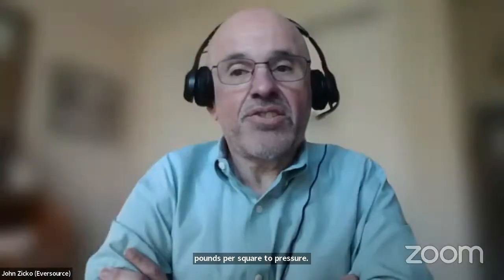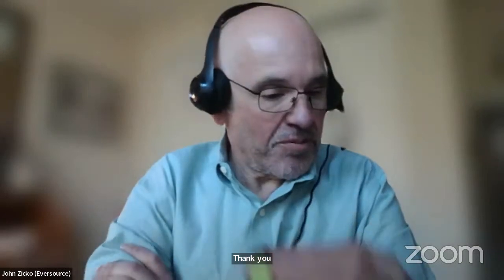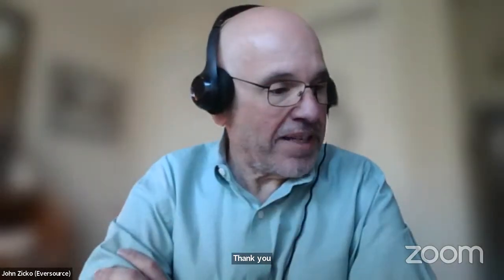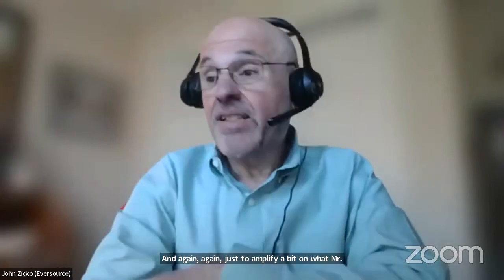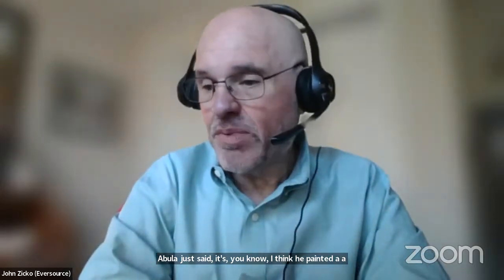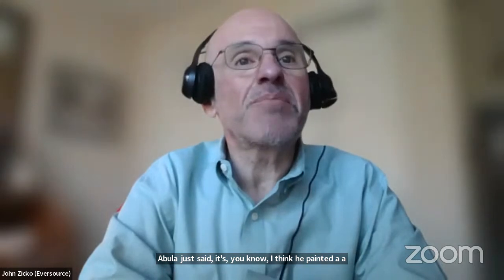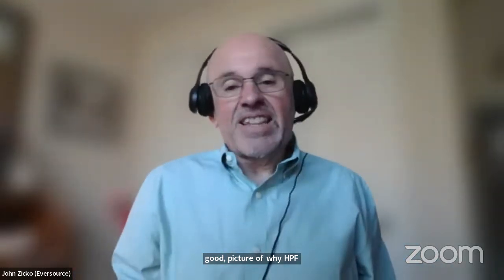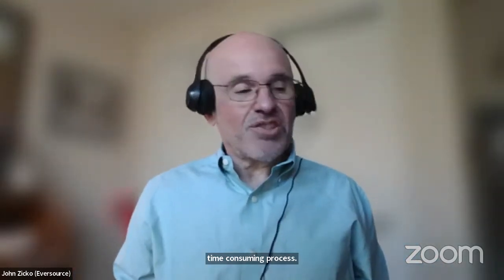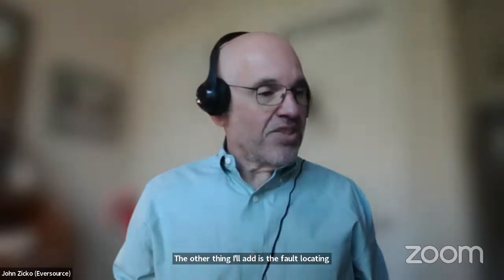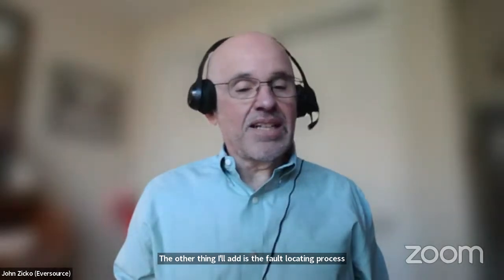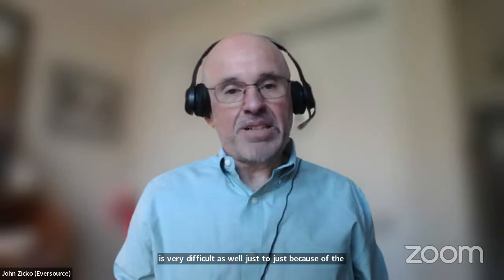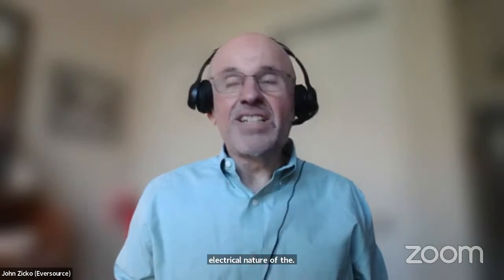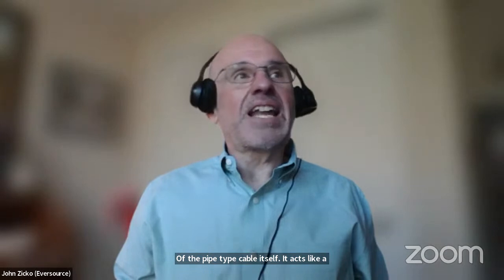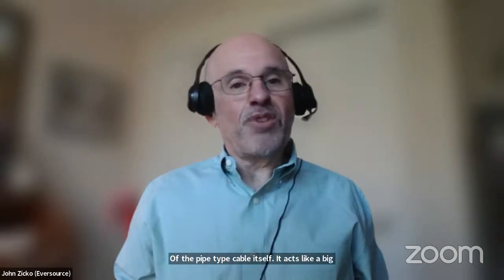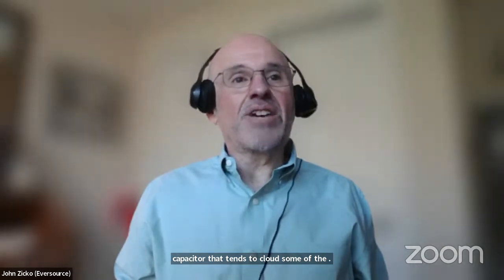So, thank you. And again, just to amplify a bit on what Mr. Abdullah just said, I think he painted a good picture of why HPFF cable repair is a time consuming process. The other thing I'll add is that the fault locating process is very difficult as well, just because of the electrical nature of the pipe type cable itself. It acts like a big capacitor that tends to cloud some of the fault locating technologies that we now have.